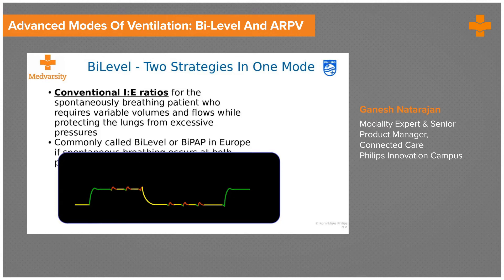This mode is also one of the lung-protective modes because it protects the lung from excessive pressures. However, there is also a chance for a patient with higher demands to displace more volume. Regarding nomenclature differences between equipment from Europe and the US: European devices call it bi-level or BiPAP, while US devices may call it bi-level or by other names like duo-level or smart-level.